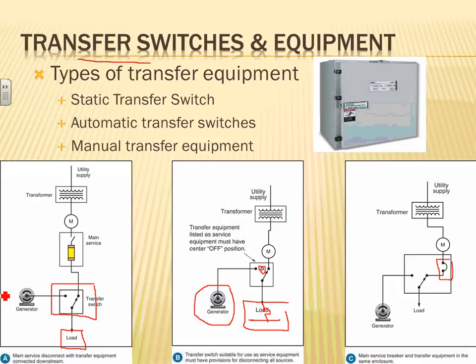Is the auto transfer switch required on legally required and emergency systems? Manual only, you can only put manual on a standby system. If you decided to go through static transfer switches, the only place I've seen them is on data centers. These electronically switch the signal. Do you guys use static for anything other than that?